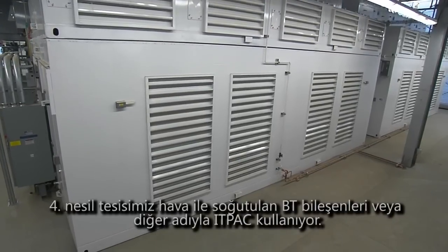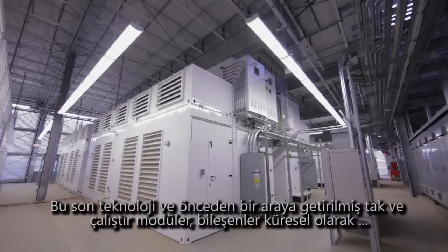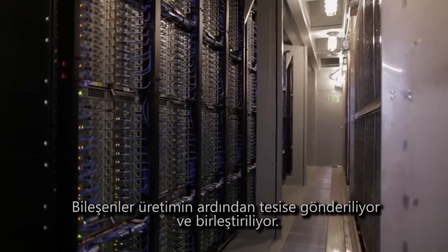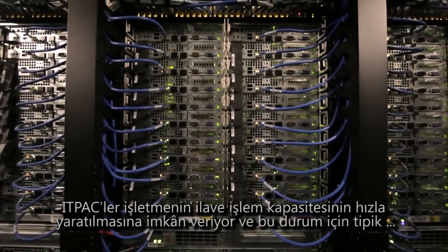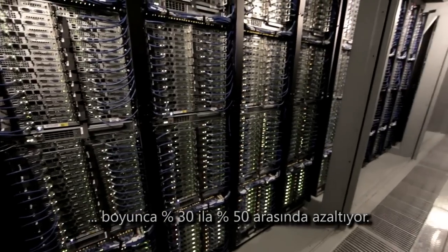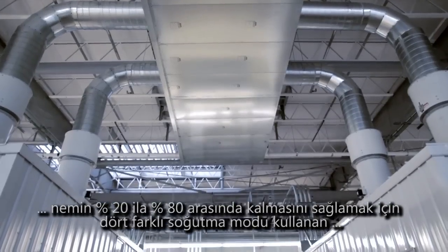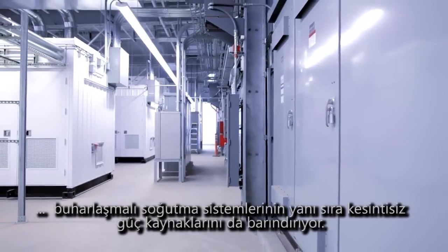Our Generation 4 facility utilizes air-cooled IT pre-manufactured components, or ITPACs. These state-of-the-art, pre-assembled, plug-and-play modular components can be manufactured in many locations through a dynamic supply chain of globally distributed vendors, and use recyclable materials such as steel and aluminum, which are then shipped on-site and assembled. ITPACs allow rapid commissioning of additional compute capacity as the business needs it, reducing the typical two-year construction time frame in half and reducing capital costs by 30 to 50 percent over the lifetime of the facility. The ITPACs also provide self-contained UPS, along with air handling and evaporative cooling systems to control ambient temperatures, with four cooling modes to ensure the inlet temperature is maintained between 50 and 90 degrees Fahrenheit and 20 to 80 percent relative humidity.